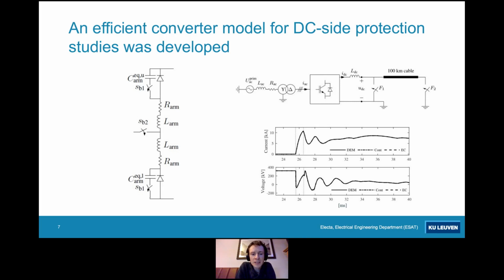So in my PhD, I developed a converter model that is suitable for DC fault analysis, and that is really dedicated to DC side protection studies. The advantages of the model were that almost all of the switches were excluded, and almost all of the control loops were also excluded, so that we have a really efficient model. And by comparing the results of this reduced model to a very detailed model, we found that we could get a very close match.